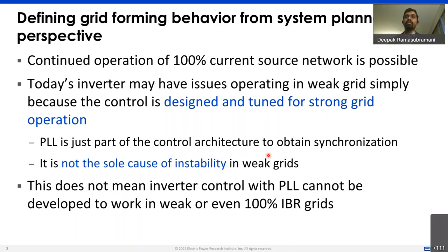Now, a lot of today's inverters may be designed and tuned for strong grid operation, but in those strong grid designs of these inverters, a PLL is only part of the control structure that is used to obtain synchronization. And when an instability occurs, that's not the sole cause of instability in weak grids, because it depends upon how that PLL is behaving with the other controls in the network. The sole blame, so to speak, of an instability shouldn't just be on the PLL. And what that results in is that if an inverter actually does have a PLL, but if it is controlled in a manner in which the current being injected by that inverter is appropriately designed, then that can continue to operate in a strong grid and a weak grid and a 100% inverter grid.